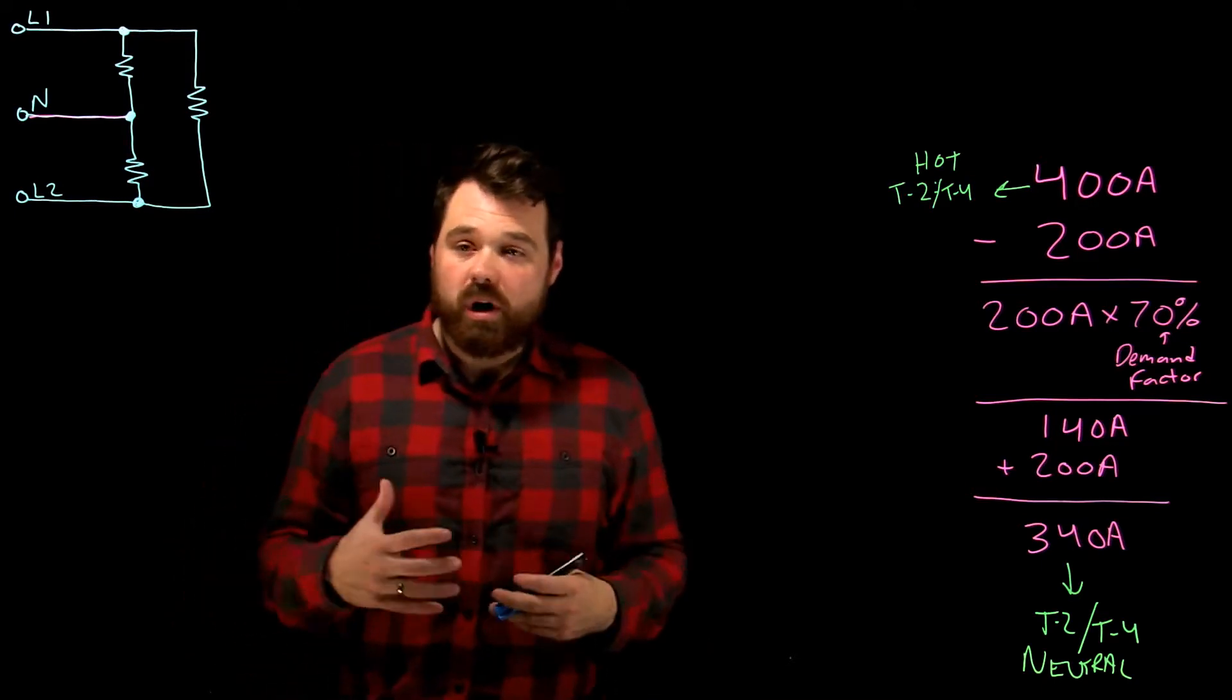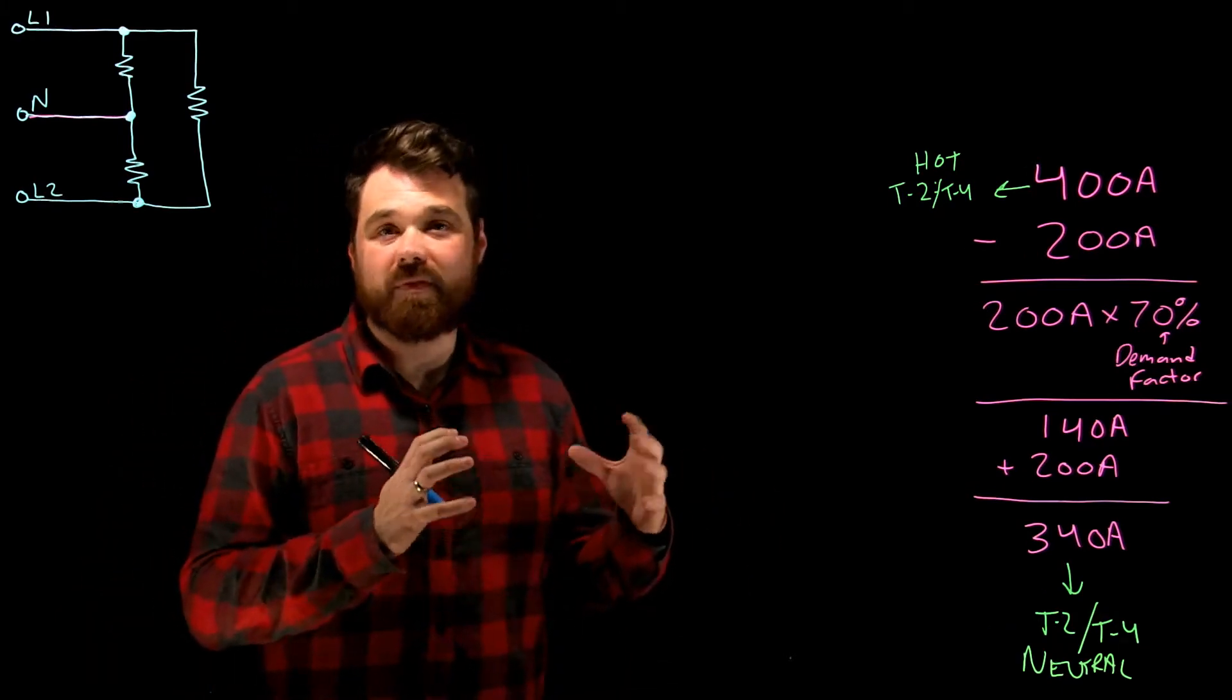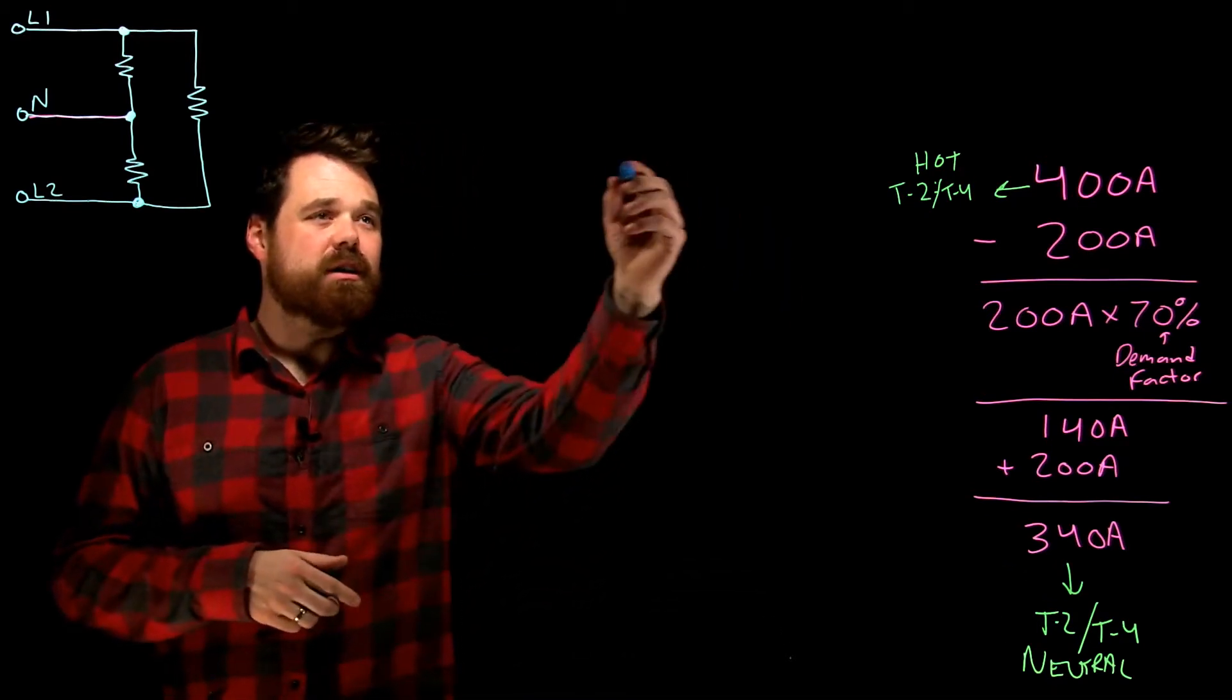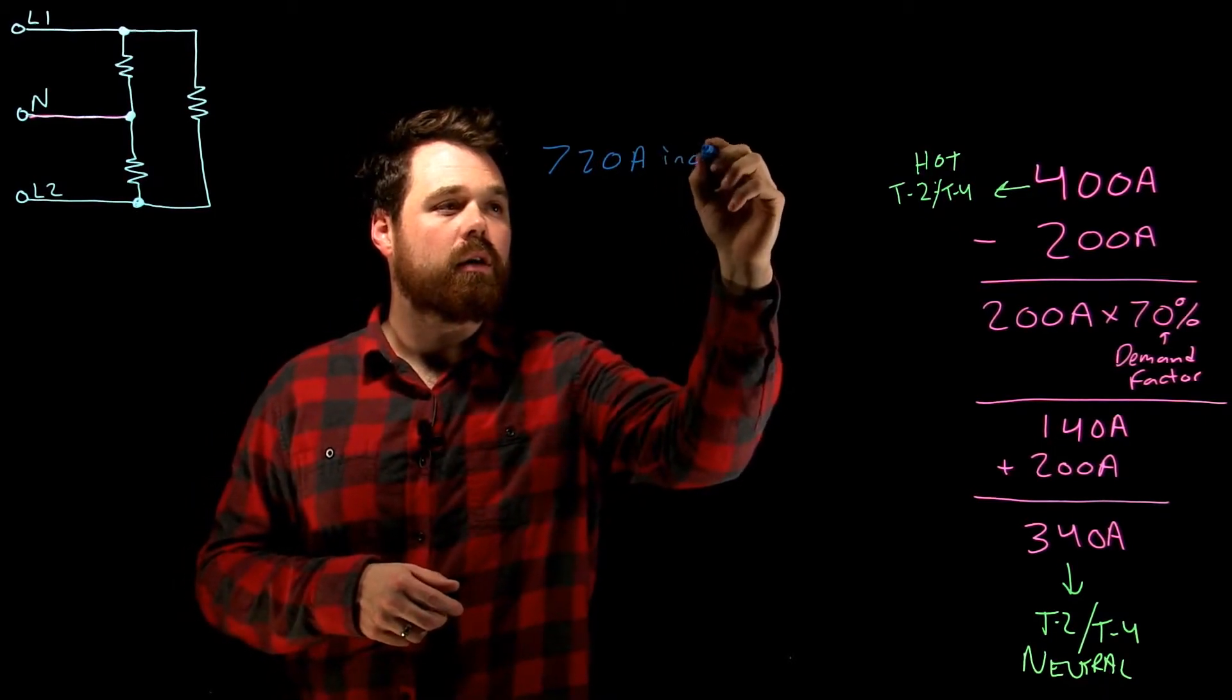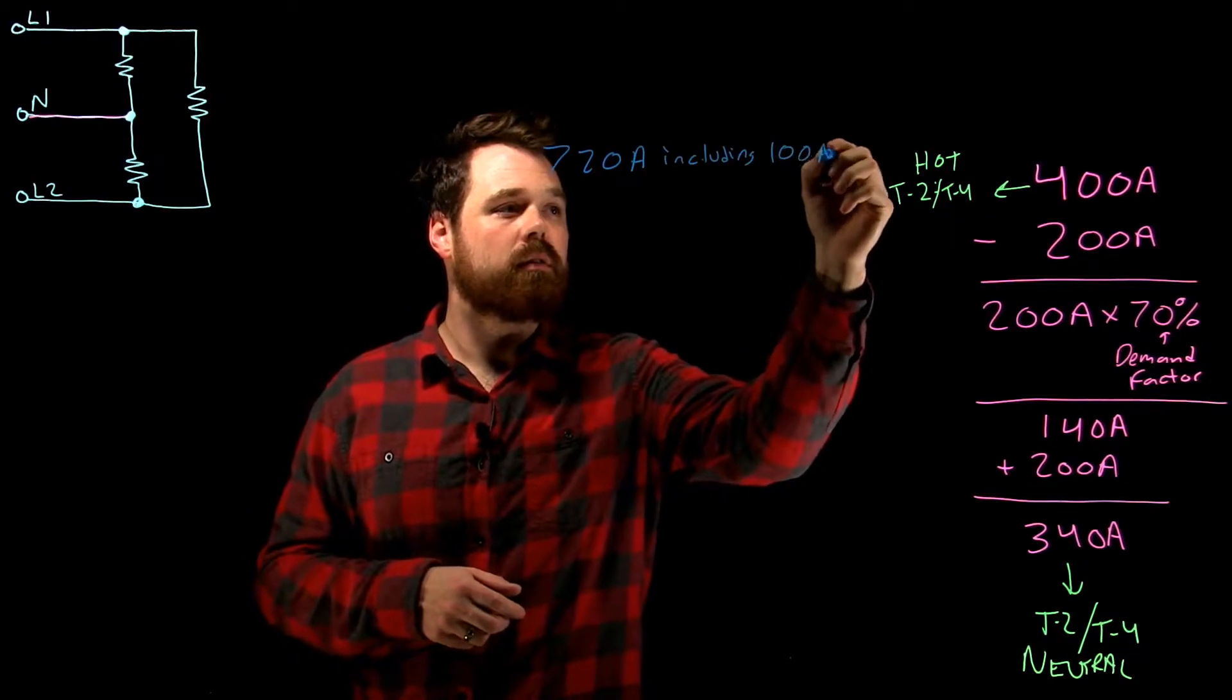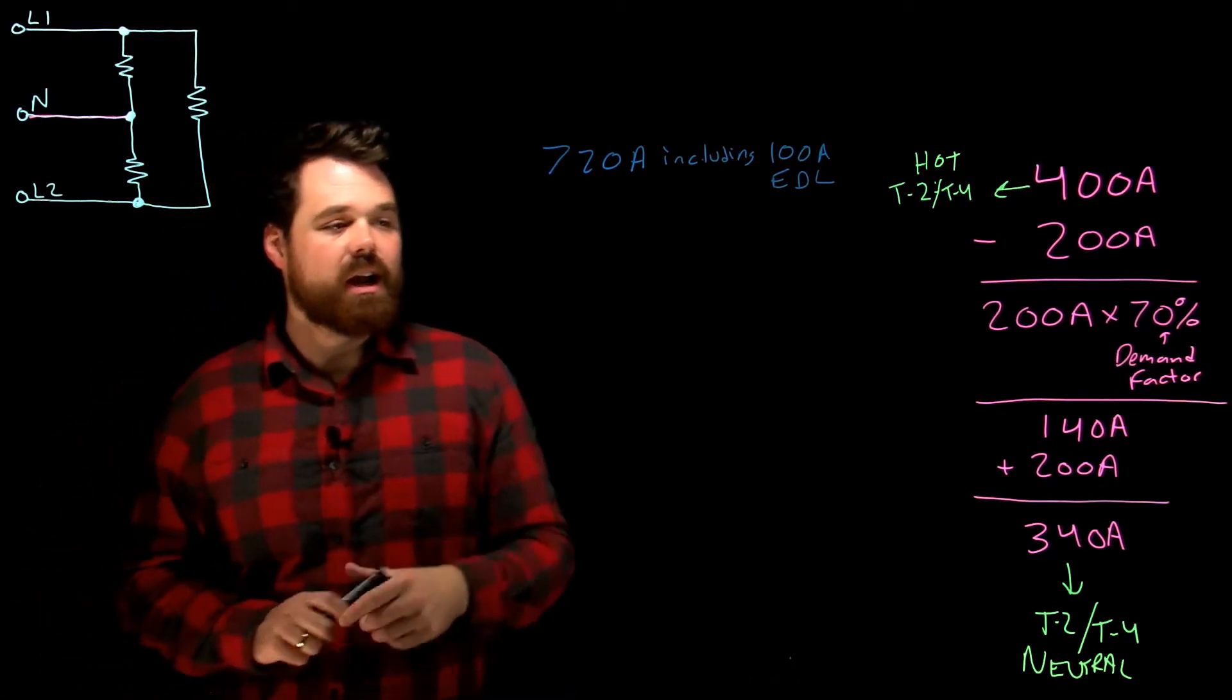So it can get a little bit more complicated. Let's say hypothetically if you did have that electric discharge lighting, which would be like fluorescent lights, things like that. So basically how that would work is let's say we had 720 amps, including 100 amps of electric discharge lighting.